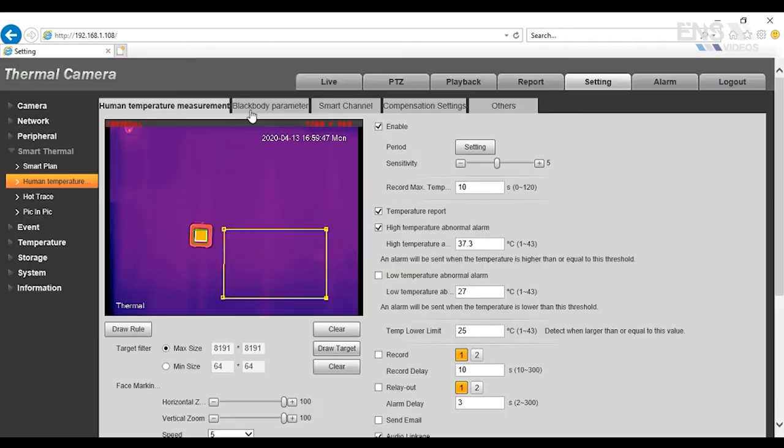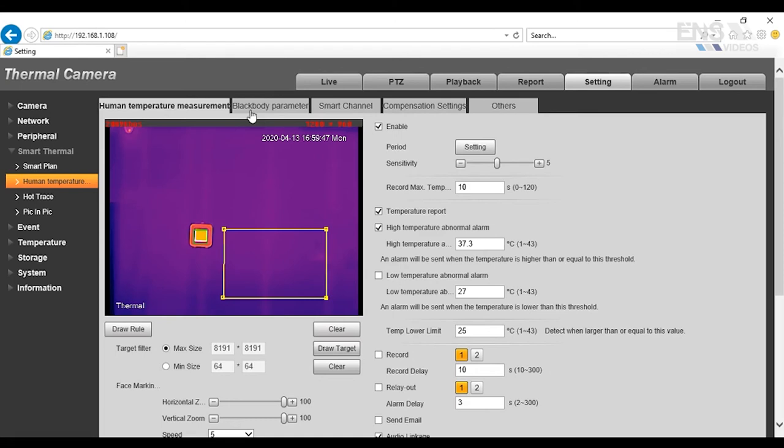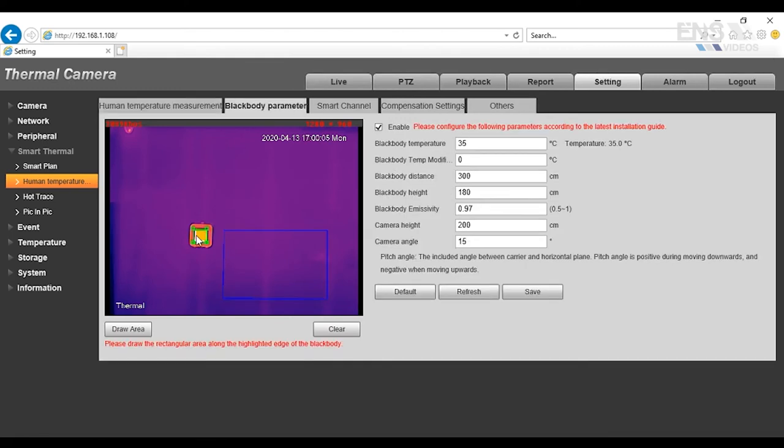The next part of the setup is to go to the black body parameter. The black body is a module that's actually facing the camera from the opposite direction. This is a temperature reference module that's very easy to set up. It allows for the accuracy of the camera to be down to 0.3 degrees Celsius, which allows for a human body temperature, which makes it different from regular thermal cameras out in the market.